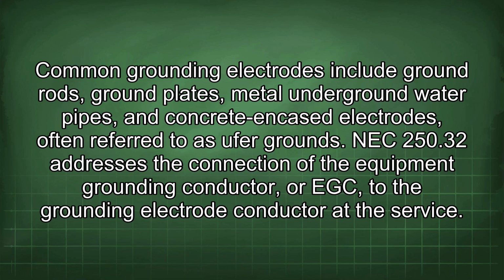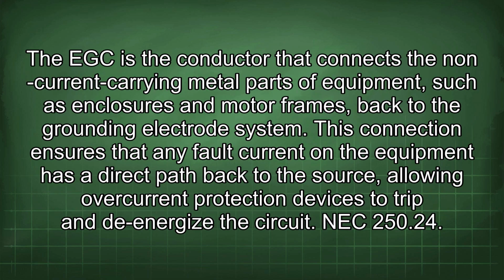the service. The EGC is the conductor that connects the non-current carrying metal parts of equipment, such as enclosures and motor frames, back to the grounding electrode system. This connection ensures that any fault current on the equipment has a direct path back to the source, allowing overcurrent protection devices to trip and de-energize the circuit.